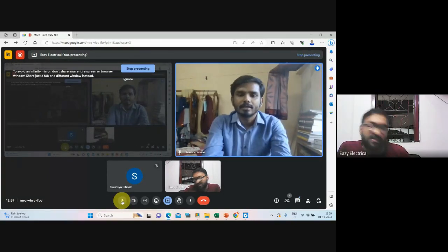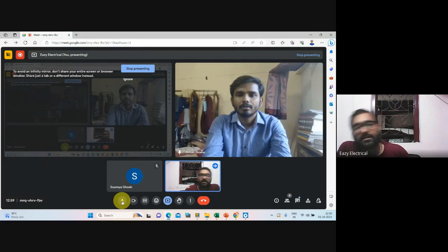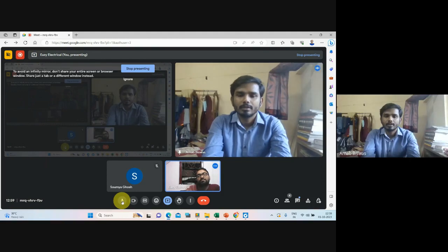Now what I am saying is magnetizing current and magnetic inrush current. Is there any difference between them? Yes, sir. Magnetizing current is a steady state current that flows throughout the operation of the transformer. But magnetic inrush current occurs when we connect the transformer to a voltage supply when the voltage waveform is at zero crossing level. A very huge amount of current gets into the transformer to develop the flux instantly. This inrush current only stays for 5 to 6 cycles.